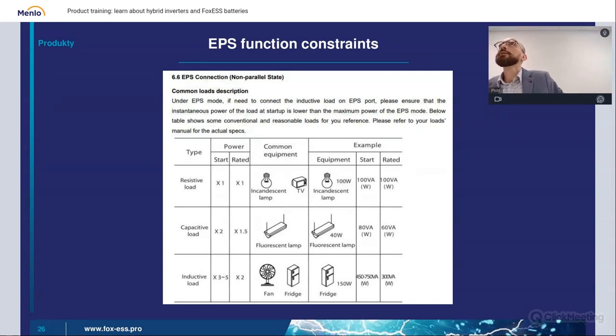I would like to tell you, of course, that there's a limit of what you can do with EPS. That's its nominal power. That's logical. You can't output more power than this inverter is designed for. Also, the client needs to know that during the emergency operation, this system and the client's grid operate as an emergency system. That's not the right time to power your very heavy loads, because you may just overpower the unit.